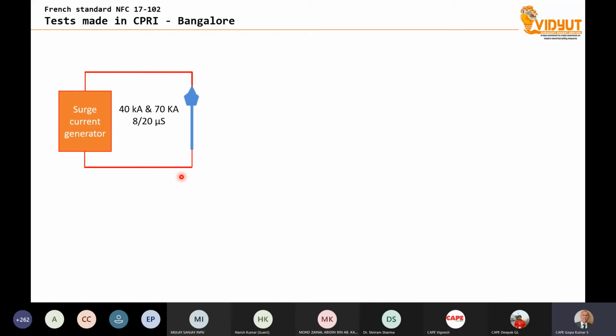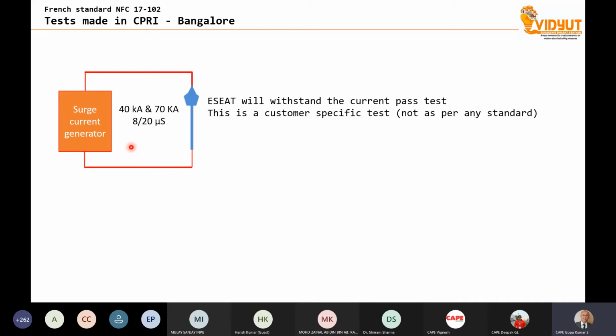Whereas in India, there is a surge current generator - two generators, one 40 kiloampere and one 70 kiloampere. The generators are connected directly to the ESE rod, with maybe 3 pulses, 4 pulses, 5 pulses, some negative, some positive, and finally the CPRI gives a certificate. You must understand this is not a test based on a standard - it is a customer specific test.